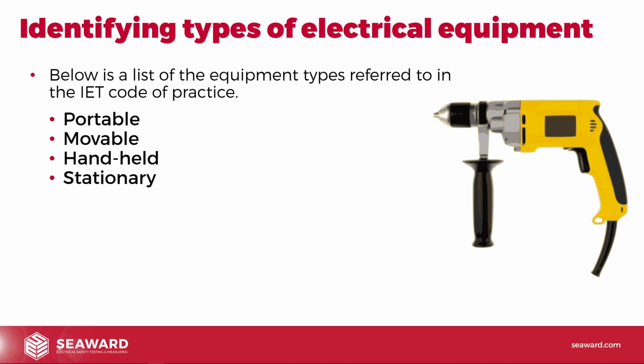Stationary equipment. Stationary equipment is things like your fridges, your freezers, your washing machines, your vending machines, all that sort of stuff. Really big chunky bits of equipment. They're not really moved around a lot. So they're seen as being slightly lower risk items, obviously depending on what they are, but generally they're seen as being lower risk because the cable isn't constantly being moved about. It's not likely to be a trip hazard. It's not likely to be unplugged and plugged in a lot of times. Generally, stationary equipment is put in place, connected to the supply, and then left alone. The chances of you being in contact with it when it goes wrong are a lot lower than, for example, portable or certainly handheld equipment.